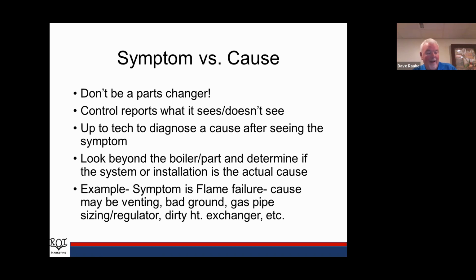And a problem I've seen is guys will say, oh, I put a new flame rod in. Well, you probably bought yourself a week, maybe 2 weeks, maybe even a month. But whatever caused that first one to read a bad flame signal, it's going to happen again. And now you're going to have an upset customer that you didn't take care of the problem the first time. So it's important to dig into things a little bit and try to figure out exactly what's going on.